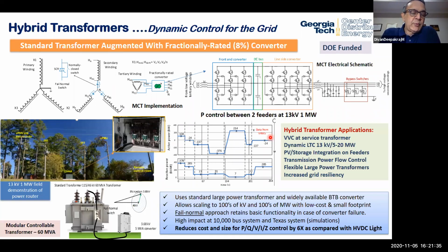One example we've been working on for many years is what we call hybrid transformers, where we take a transmission level or distribution level transformer and add a small, fractionally rated power converter in the neutral leg. This can use traditional power electronics that is readily available, and achieve a lot of functionality that HVDC light can do, in terms of power routing, VAR injection, and voltage regulation.